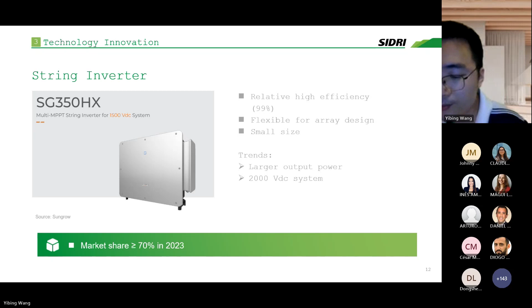Second, the inverter. Since inverters are smarter than before, some manufacturers now call it a controller. In China, string inverters have a 70% market share in scaling PV stations. We choose string inverters usually for their higher efficiency, especially in areas where irradiation is not uniformly distributed. To pursue higher system efficiency, the industry is now working on larger output power with a 2 kV DC system, meaning raising the maximum input voltage to 2 kV. This allows bigger string sizes and reduces DC line losses.